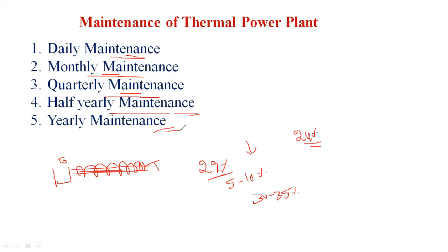The boiler is inspected once or twice a year. Again, a separate inspection is there. The boiler committee visits, inspects, and gives a report. The boiler condition should be either good, average, or bad. Based on that, maintenance is required again, or else we can replace the complete boiler system.